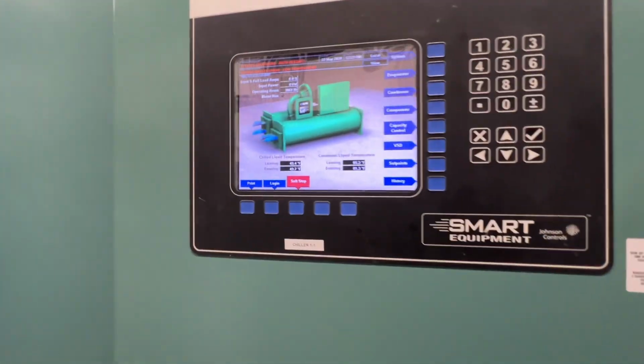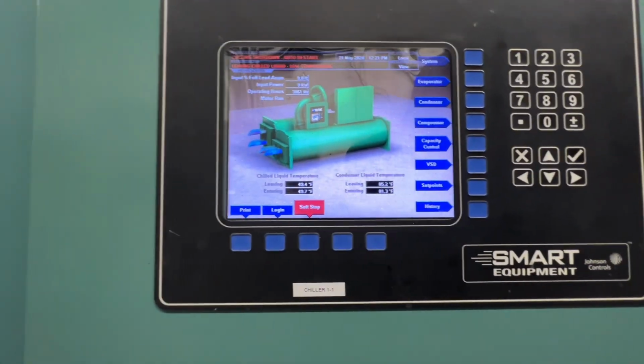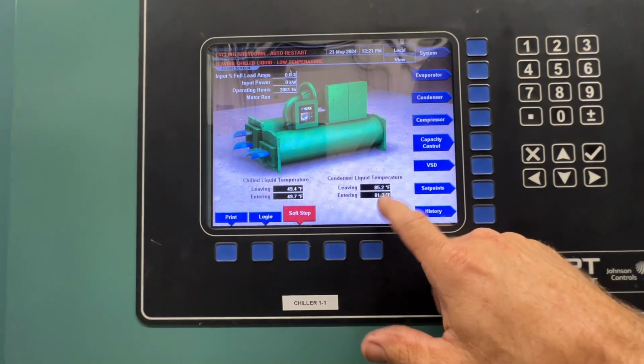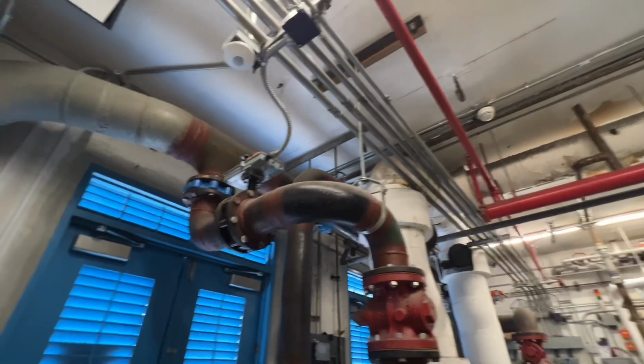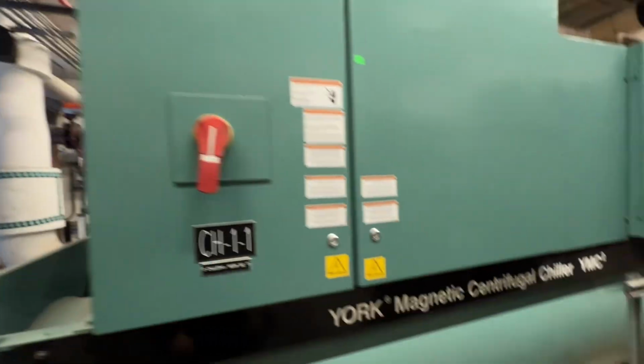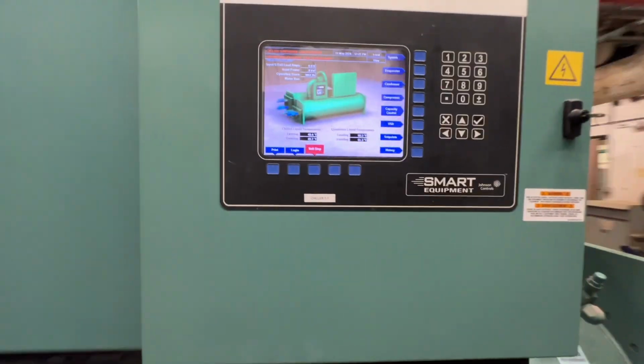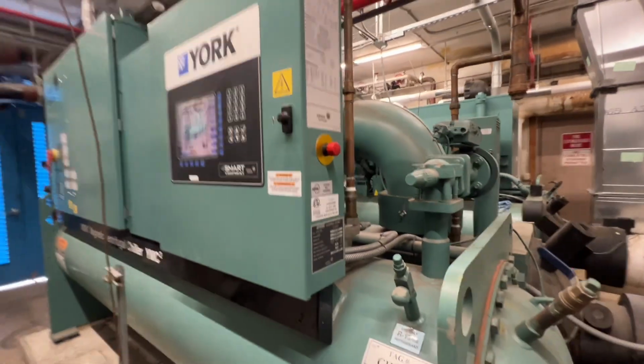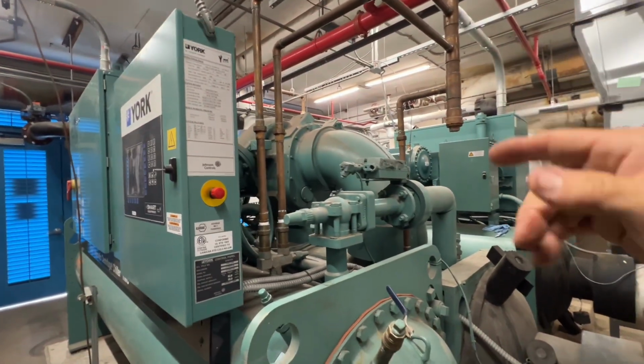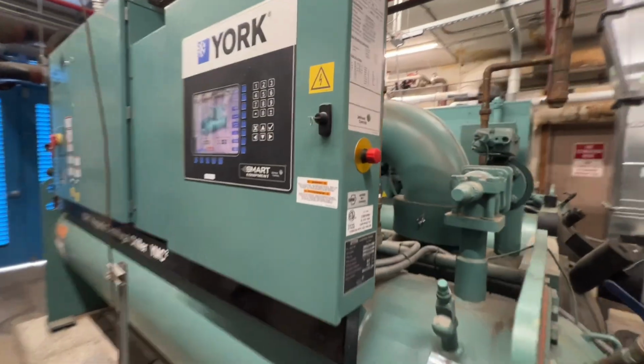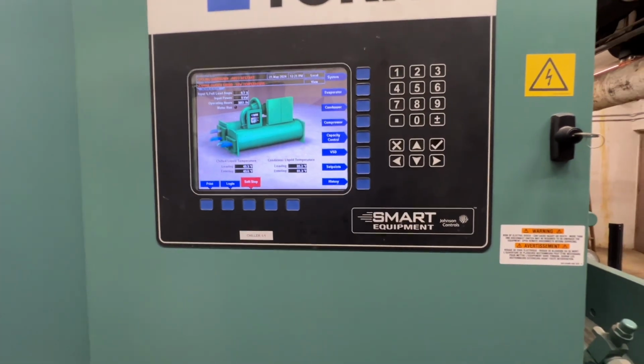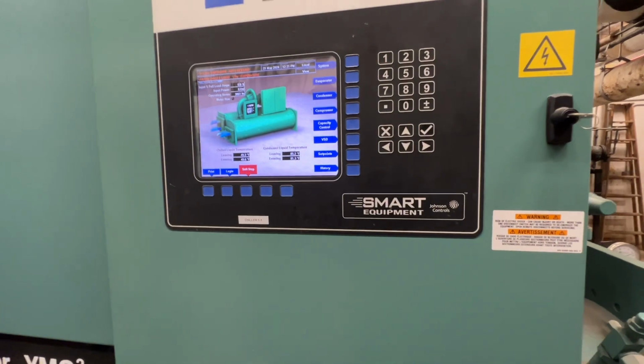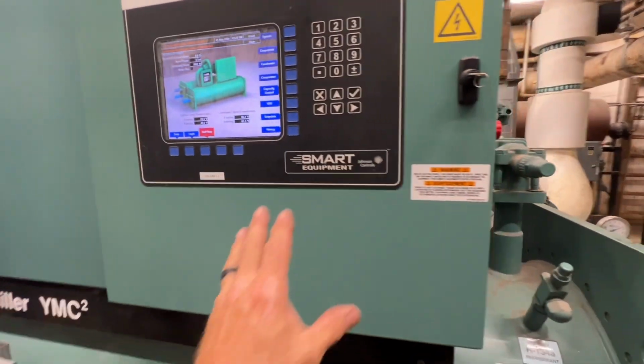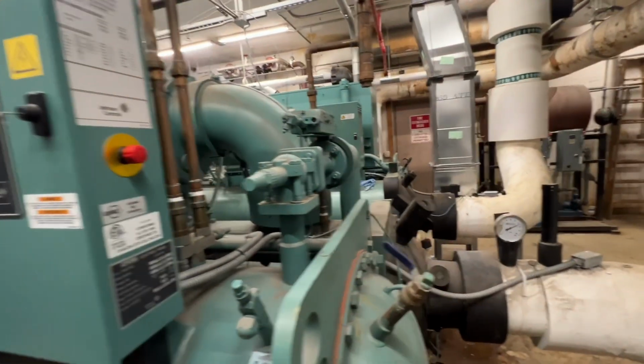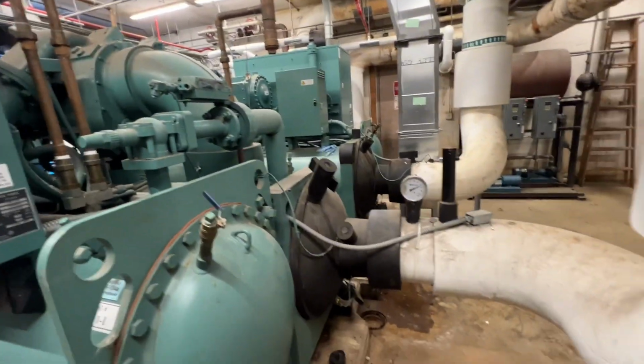All right, so back to 1. See, our leaving chill water temperature is 49. And let's see if our isolation valve is off, which is good. We did have one issue still with our chiller 2 isolation valve. It does not shut off when that turns off, but that chiller runs almost all the time anyways, and is carrying the bulk of the load. This is a 200-ton chiller. Chiller 2 is 300 ton.